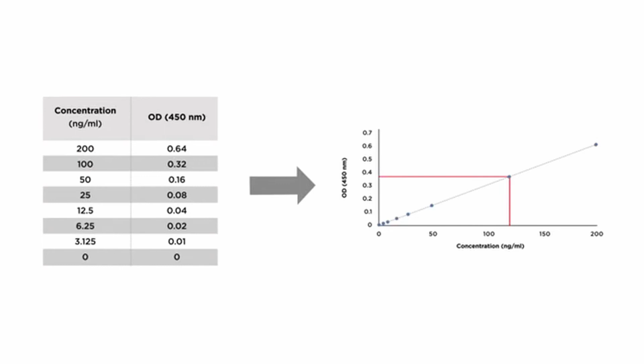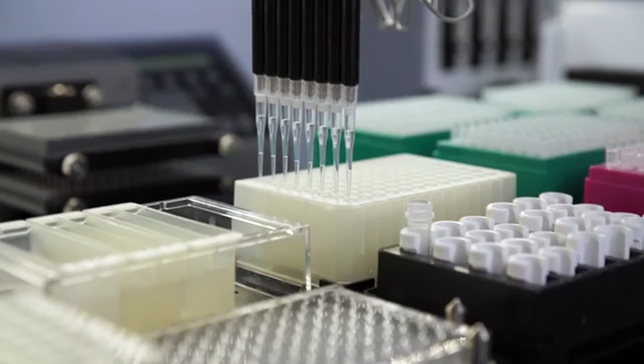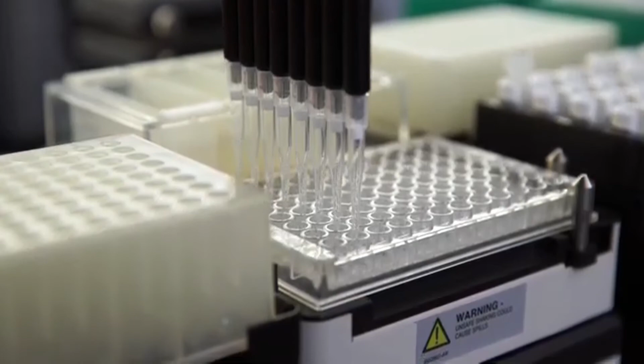ELISA quantification is based on extrapolating a standard curve. A poor standard curve can jeopardize your experiments and samples. One way to improve the standard curve is the accurate pipetting of standards. Biomek software offers versatile pipetting control through pipetting templates to fine-tune the pipetting based on the reagent and labware so that you pipette out every last drop. The Biomek Span-8 pod can accurately transfer volumes anywhere from 0.5 microliters to 5,000 microliters.